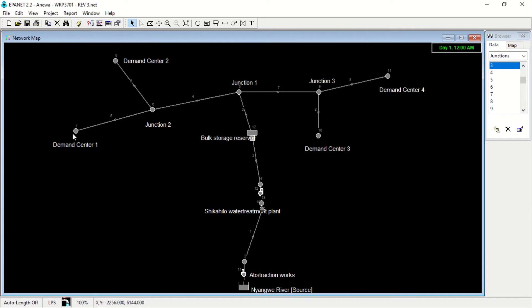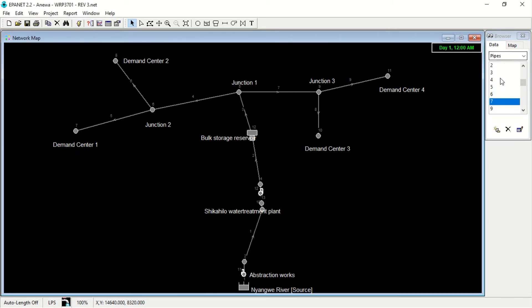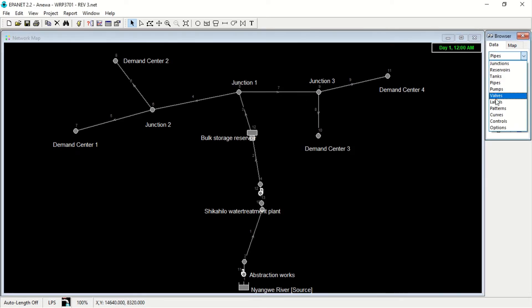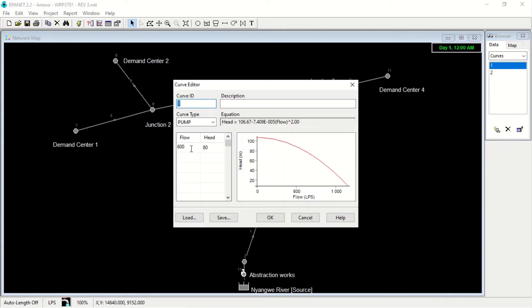We have our demand centers one, two, three, and four, as you can see. Then for each pipe, you can see the length, the diameter, and the roughness. When you go to data and do your curves, you can see the curve here: we have our flow of 600 liters per second and the head is 80 meters. This is the graph representing the relationship between the head and the flow.